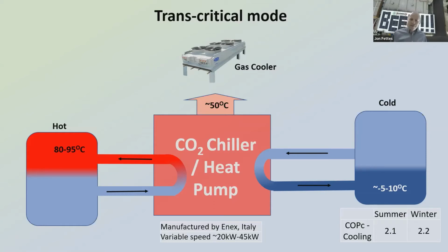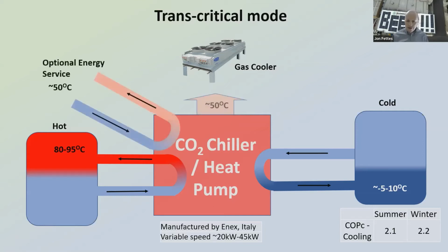If the feed from the bottom of the hot tank there becomes warm, the gas cooler will cool it and return the CO2 back to the compressor at a viable temperature for the cycle to continue. In practice, the gas cooler will operate most of the time. By adding a second heat exchanger at the hot end, we can value add the process and use this waste energy for an optional mid-temp heat service, such as space heating.